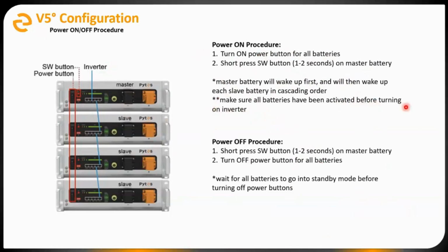You're going to wait until all the batteries are activated and in standby before we turn the inverter on. So in other words, we want all the batteries ready to go and reporting before the inverter powers up. To turn off the system, just for reference, it's basically the opposite. You do the SW button, short press and hold on the master, put them all in standby, and then turn the power switch off to all the batteries. You're going to wait until the batteries go into standby before you turn the power buttons off.